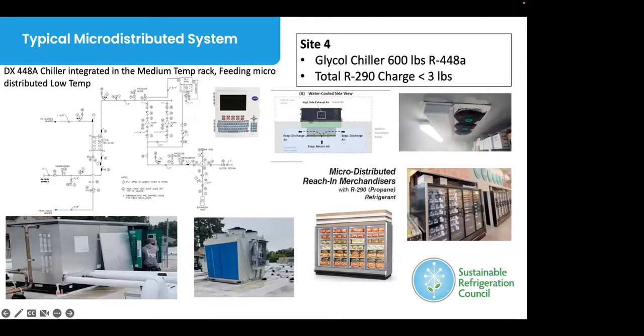And then the last system, this was again a site where we had the opportunity to replace all the cases, and this system had an existing direct expansion rack that used 200 pounds of R404A and 230 pounds of 407A. With this system, we used a micro distributed system that has the refrigeration system built in to each case. So there's a chiller built in to remove the heat from those individual units. These were Hussmann cases with the cassettes on top of the cases and the walk-ins.